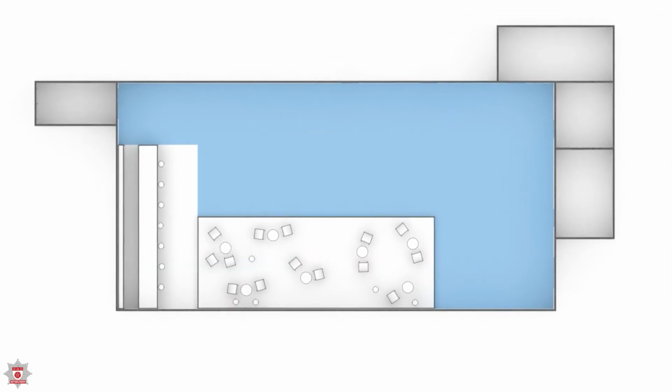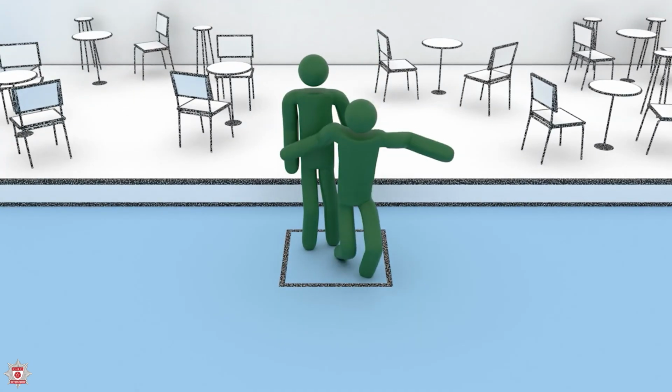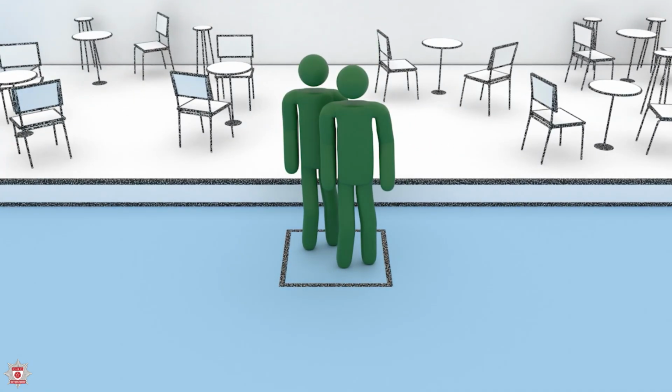The occupancy factor for this area is 0.5, which means that we can fit 2 people into each square metre in an assembly hall, such as a dance floor in a bar, pub or club. Now we know our occupancy factor and we know that we can fit 2 people per square metre, we multiply our floor area by 2.